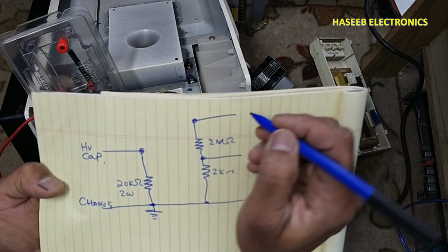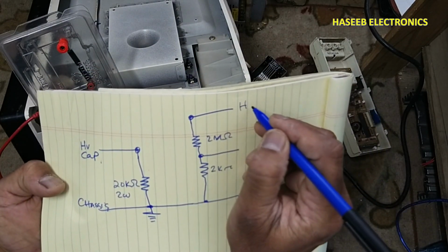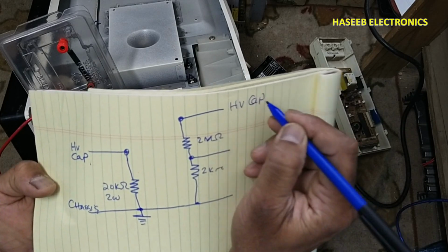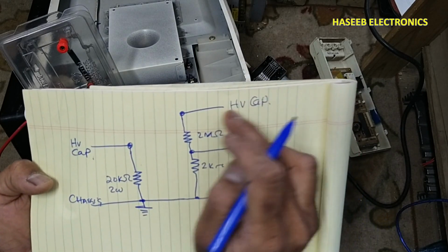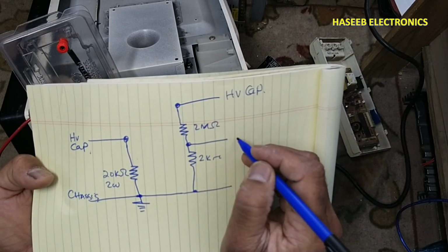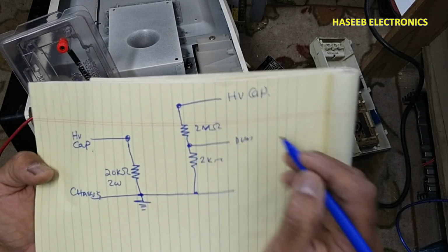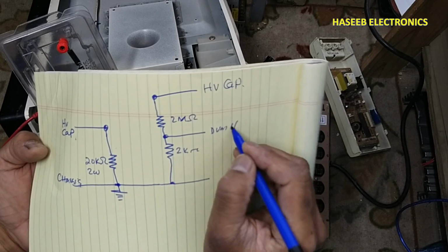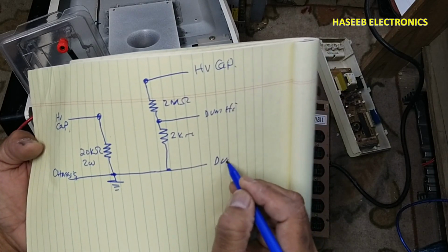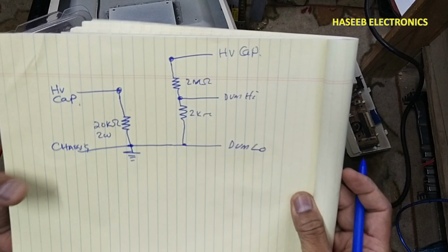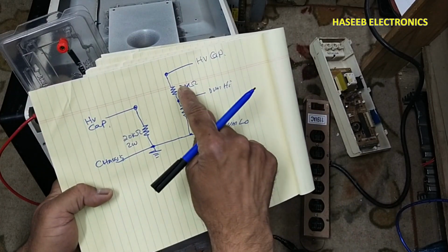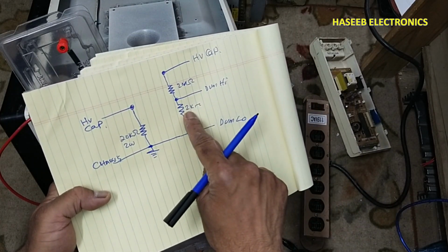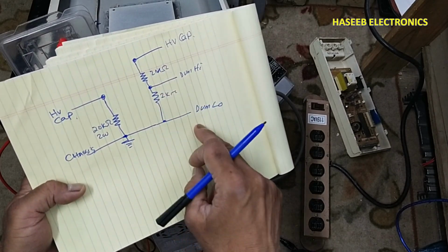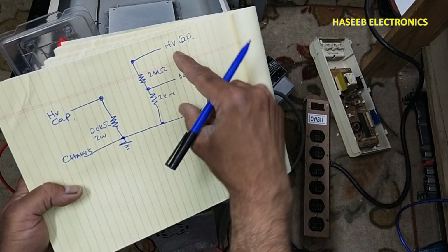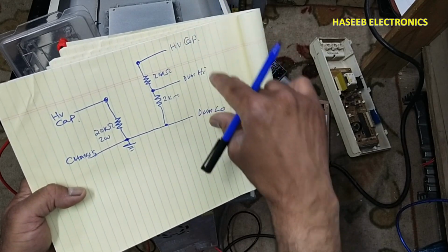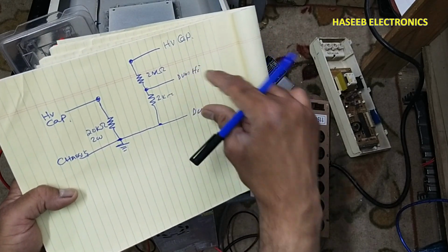Now we will measure it practically. This will go to high voltage capacitor, and we can also check high voltage transformer here. This will go to DVM high, DVM low. So we are using 2 mega and 2 kilo ohm resistance, so it is 1000 ratio. If you provide 5000 volt here it will read 5 volts.